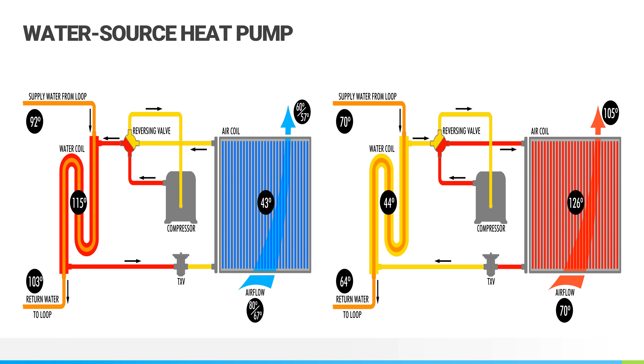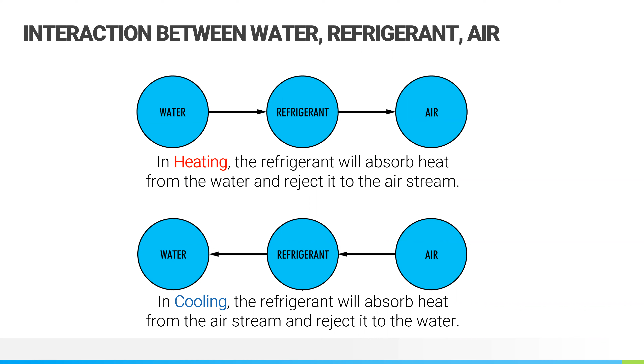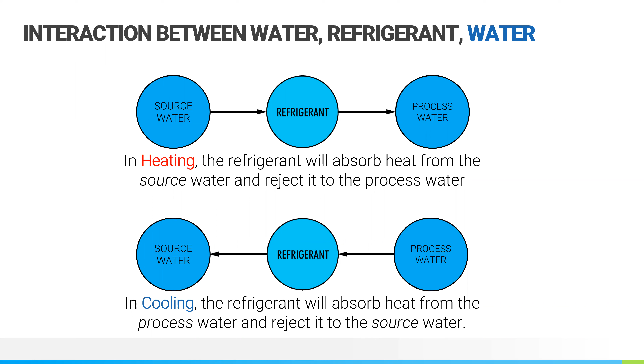You've also got what are known as water source heat pumps. The big difference here is that instead of having an outdoor condenser, you've got a water loop that is carrying that energy to or from the heat pump unit. On the simplest side, you've got a water loop transferring to the refrigerant to air in heating mode, and in cooling mode you've got the opposite, where the refrigerant is absorbing heat from the airstream and rejecting it to the water. There are also water-to-water heat pumps, which are really no different than water-to-air, except you're transferring heat energy to and from what I call a process water loop, like for radiant floors, radiant cooling, snow melt, those types of applications that you'd see in the HVAC world.